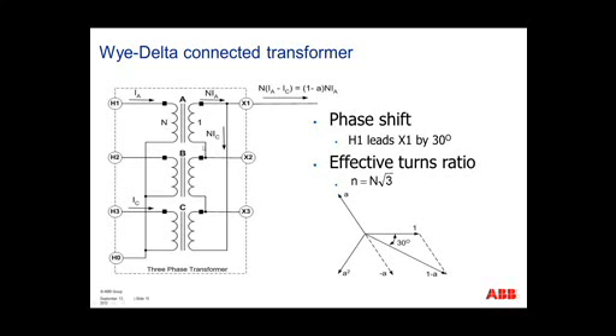These Wye-Delta transformers typically are seen a lot in your step-up installations. Typically the delta of this Wye-Delta is connected to the generation side, and the Y side, or the high voltage side, is connected to your transmission side. A benefit of this is it isolates any zero sequence currents coming in the generation plant. It isolates the transmission system of these zero sequence currents.